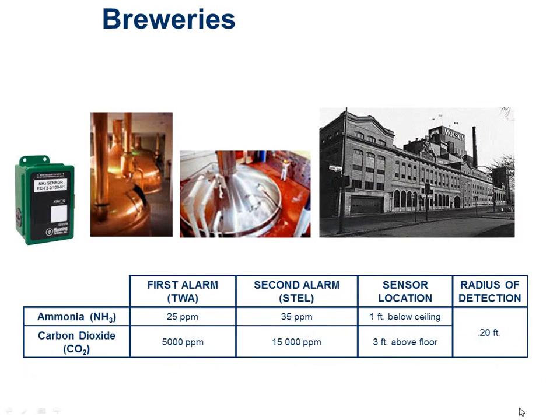Now, previously I said carbon dioxide was not dangerous, right? But I was also talking about small levels like you'd find in an office building. Here I want to know if something's out of control. If I have 10,000 parts per million, obviously I have some kind of leak and something's not right. So I need to deal with that. So typically we control that below 5,000 parts per million and we alarm it at 15,000 parts per million.